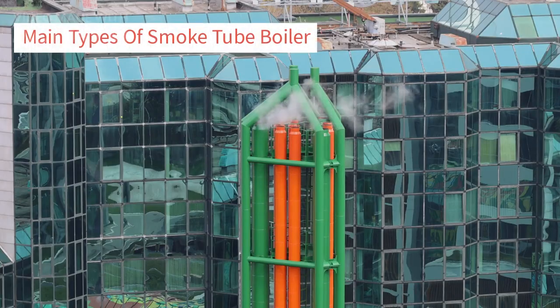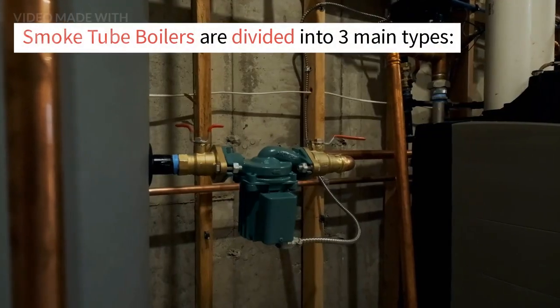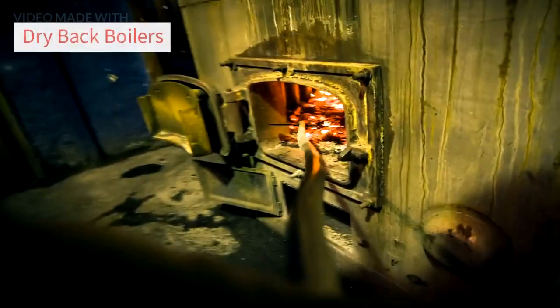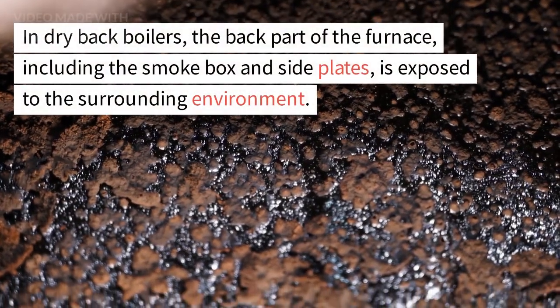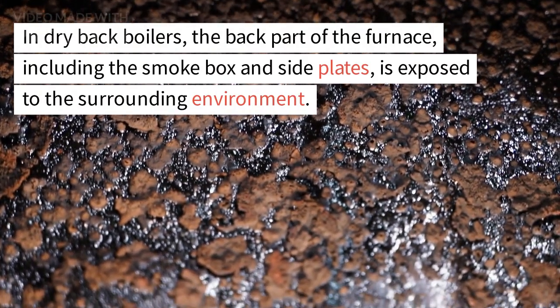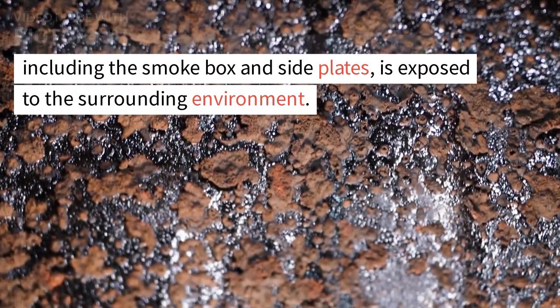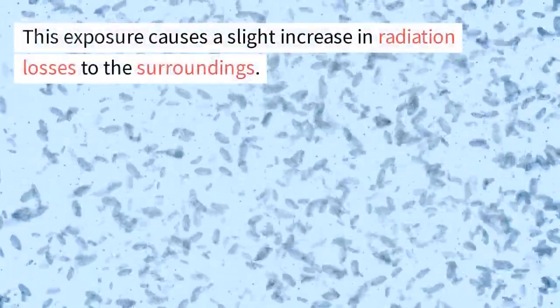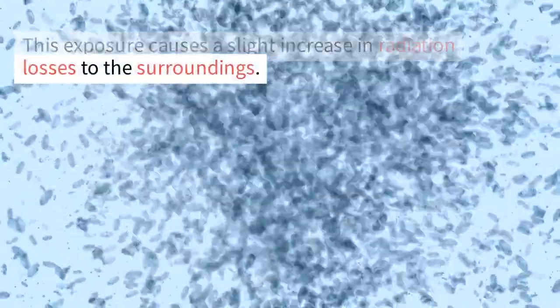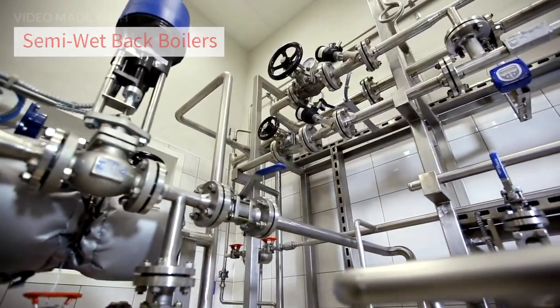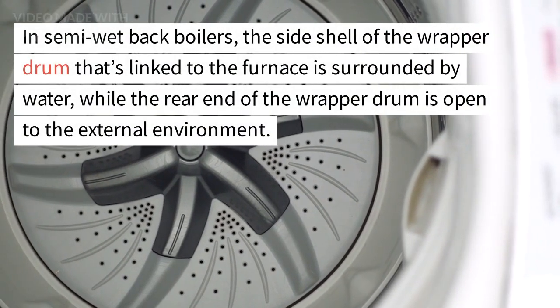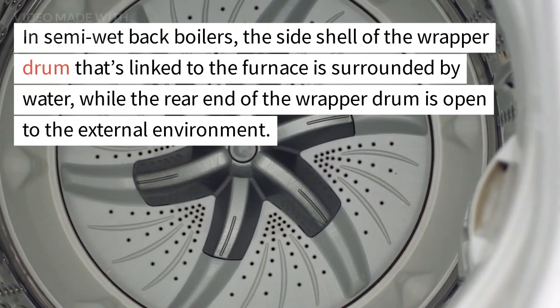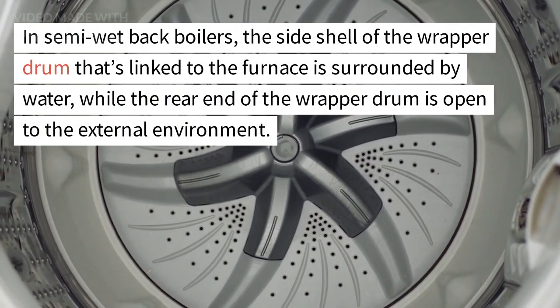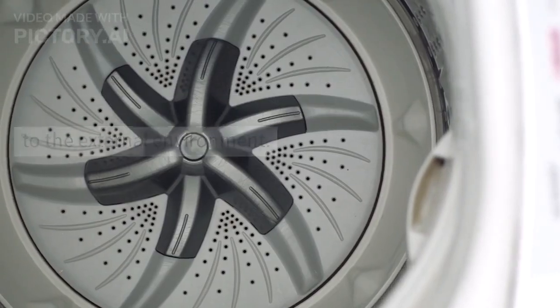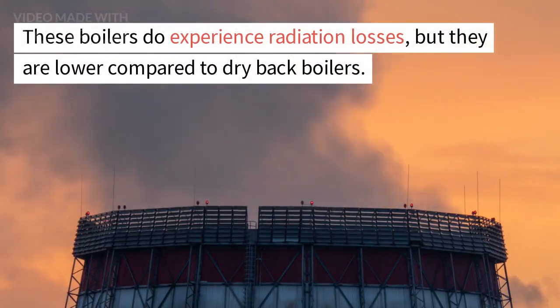Main types of smoke tube boiler. Smoke tube boilers are divided into three main types. Dry back boilers. In dry back boilers, the back part of the furnace, including the smoke box and side plates, is exposed to the surrounding environment. This exposure causes a slight increase in radiation losses to the surroundings. Semi-wet back boilers. In semi-wet back boilers, the side shell of the wrapper drum that's linked to the furnace is surrounded by water, while the rear end of the wrapper drum is open to the external environment. These boilers do experience radiation losses, but they are lower compared to dry back boilers.